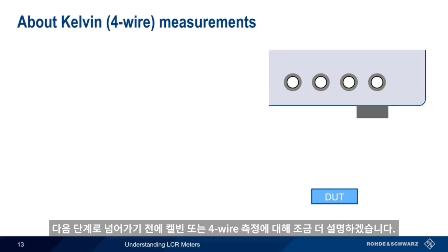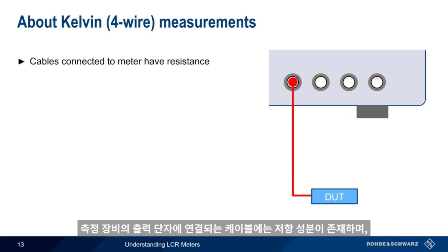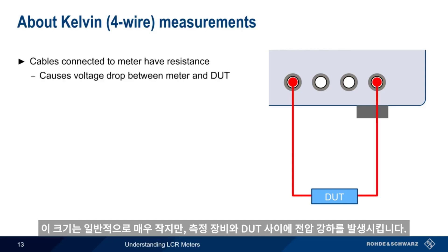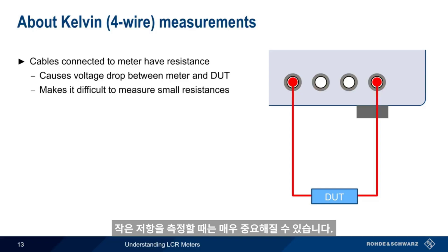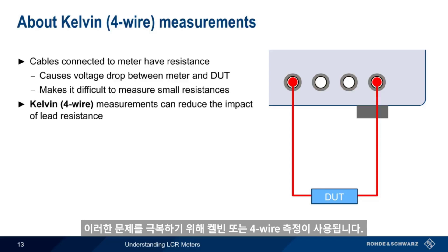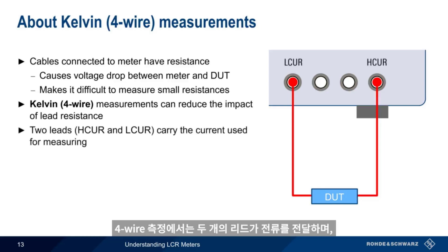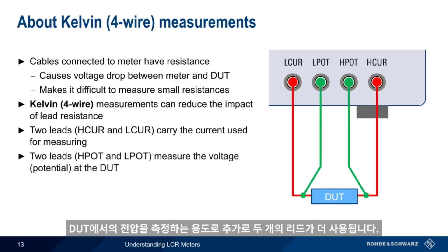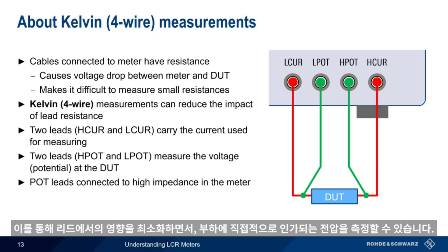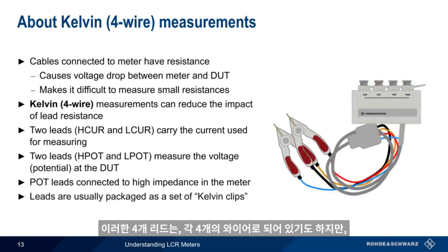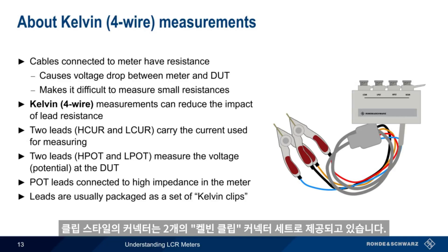Let's discuss Kelvin or four-wire measurements. The cables connected to the meter have resistance, and although this resistance is typically very small, it does cause a voltage drop between the meter and the device under test. In a four-wire measurement, two leads carry the current, but two additional leads measure the potential or voltage at the device under test. These leads are connected to a very high impedance, so there's almost no current flow and therefore almost no voltage drop. This allows the meter to measure voltage almost directly at the load, with minimal impact from the test leads. In most cases, these four leads are packaged as a set of Kelvin clip connectors with four wires but only two clip-on-style connectors.